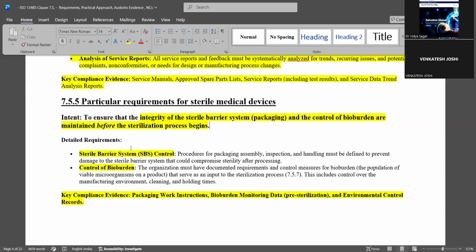Generally, we sterilize the devices after packing. What we call the sterile barrier system, or we use some pouches. Basically, everybody will use Tyvek pouches because it has a lot of pores, through which it can be sterilized. But after sterilization, once I take that sterile product outside, there should not be any intrusion of microorganisms through the packing or the barrier system into the device. Otherwise it will again become contaminated. So that is the importance of the sterile barrier system or packing.